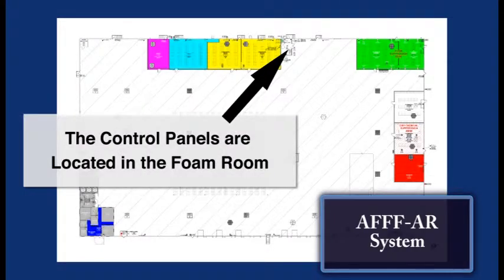The control panels for the AFFF-AR equipment are located in the dedicated foam room where the AFFF-AR tanks and valves are located. This permits access for maintenance and operation of the panel without entering the spaces served. This is designed to minimize risk to responding emergency personnel if the system must be accessed for information or reset during an emergency.